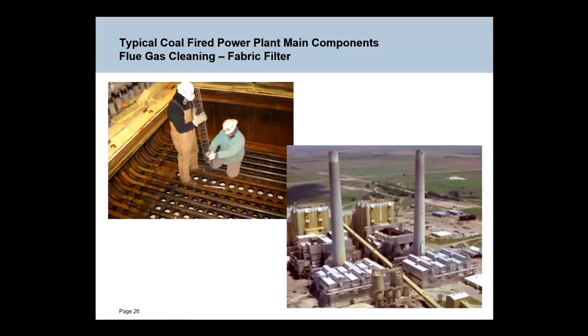Then flue gas cleaning. As we've said, the gas that comes out of the boiler has dust in it, ash, and we need to clean that ash out, otherwise it's going to come out of the stack and go across the countryside. Two main technologies. One is fabric filters. These are like very long, thin vacuum cleaner bags. You can see these are being installed here in this picture, and there will be thousands of those bags in one unit, and they are regularly mechanically shaken to shake the dust off as the dust collects, and then that dust is sluiced away and taken to the ash dam.